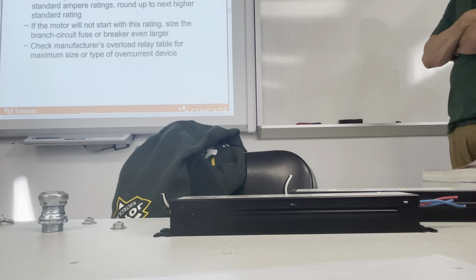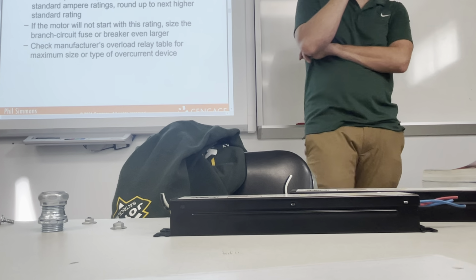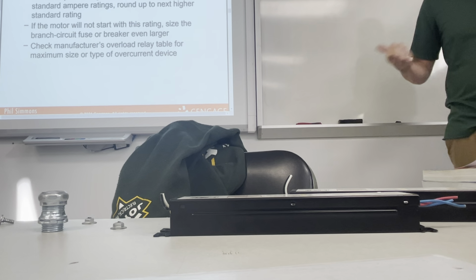When ampere rating or setting does not correspond to standard ampere ratings, round up to the next higher standard rating. If the motor will not start with this rating, size the branch circuit fuse or breaker even larger. Check the manufacturer's overload relay table for maximum size or type of overcurrent device. Yeah, like I said, this motor could be rated for 5 horsepower, but it's just turning something that has a lot of friction, like a conveyor belt that hasn't been greased properly. That startup amperage by itself is going to be crazy. You add in more friction, a longer belt, anything, and that amperage is going to increase that much more. So you need to have your system sized to be able to take that high initial current so it can stabilize back down to a lower number.